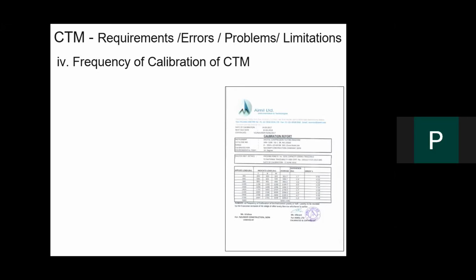In some places they have 4 to 5 proving rings all over India. They work with different types of machines in different locations. They have their offices, but they have only one calibrated machine or proving ring with them. So when we ask for the calibrated proving machine and their certificate, they say, 'no, this is not available here, sir, it's in Bombay. We have to check the calculation with our other office, we will ask the people, we will talk to them, and then we will realize whether it is working.' So this is the major problem.